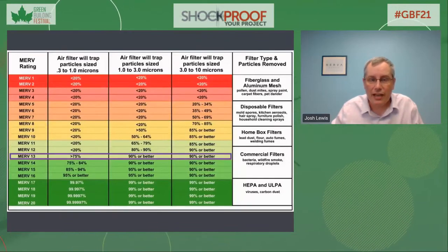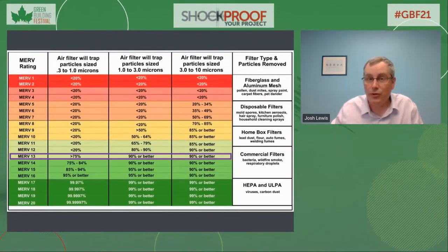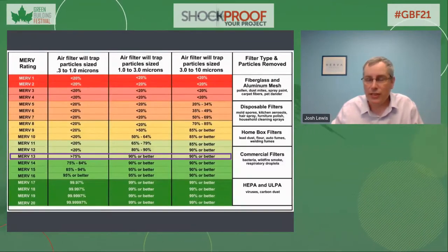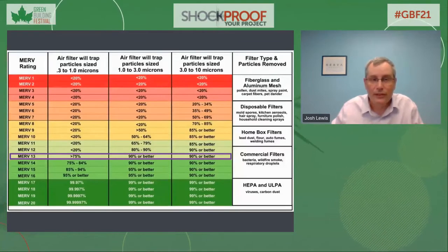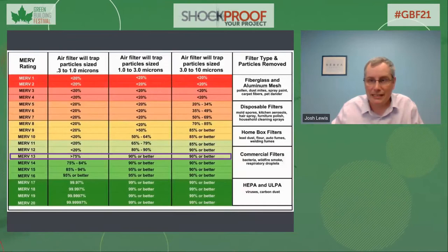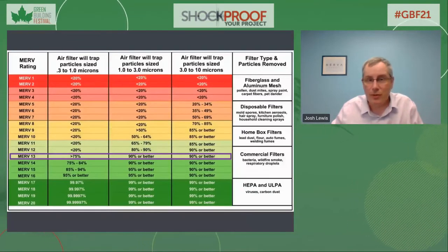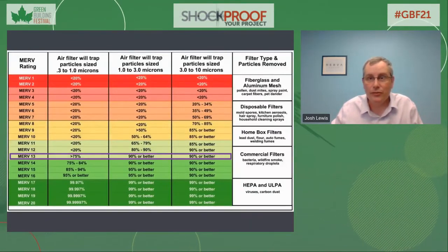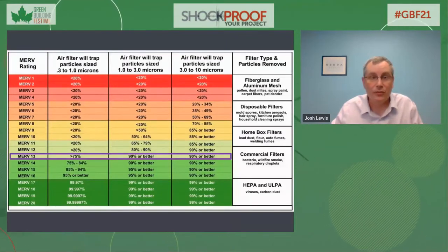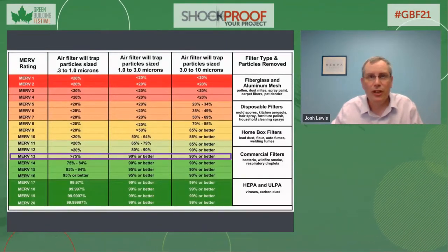Now, according to ASHRAE, filters with a MERV 13 rating are the minimum recommended for the effective capture of COVID-19, and they are also effective against a large range of other types of viruses, bacteria, and other contaminants. However, this is an upgrade from the baseline state of most HVAC systems, which in the past have typically been equipped with pleated filters with a MERV 7 rating, or even worse, media-style filters, which only capture large debris and thus are practically useless against most contaminants.